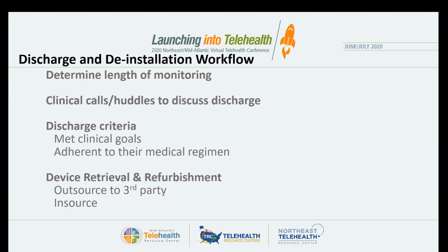And then you're going to have device retrieval and refurbishment. Are you going to do that yourself? Or are you going to send somebody out into the home to get that equipment? It has to be sealed in a plastic container or a trash bag for 24 hours, placed in the dirty location of your car or vehicle, taken to the dirty location within your organization to sit for 24 hours, and then somebody needs to physically clean the devices and put it back on the shelf.